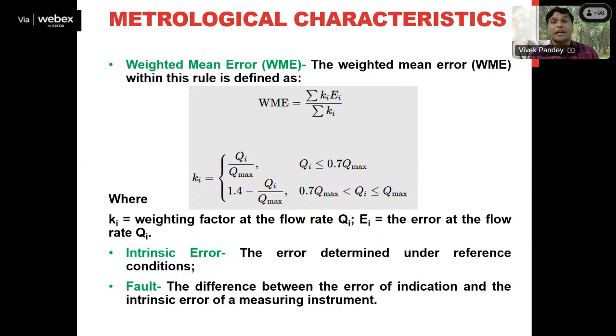But apart from that accuracy error, which is basically calculated at different flow rates. Suppose we are performing the accuracy test on a gas meter, it should be performed at a minimum flow rate, maximum flow rate, transitional flow rate, and at other flow rates decided between minimum and maximum. So error can be observed for a gas meter at a certain flow rate. However, this weighted mean error is a very interesting parameter which gives you the accuracy of the measuring instrument, which is the gas meter in this case, with respect to all the flow rates specified between minimum and maximum flow rates. That means, whatever flow rates we select between minimum and maximum, what is the average error, or you can say the effective error.